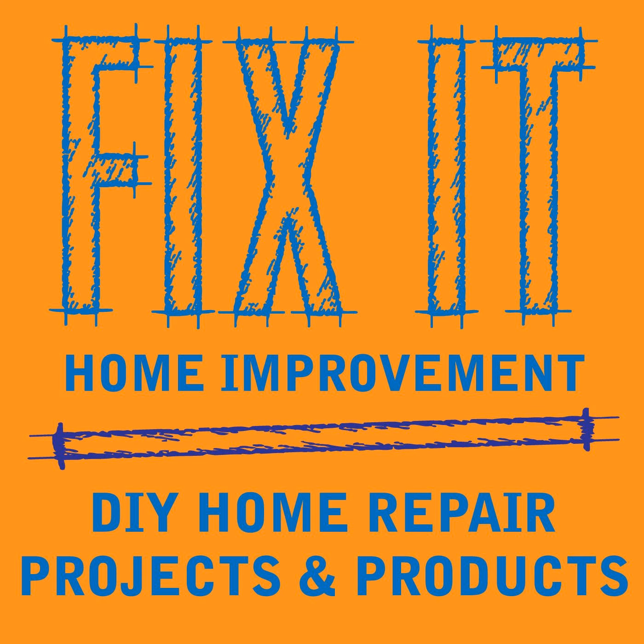The key to finding out what wires go where, let's say you removed your old outlet and you didn't mark which wires were on the line or the load side, or let's say you had a traditional outlet and now you're changing it to a GFCI, you have to know what side is line and what side is load. So you turn off the breaker to this circuit and you're going to separate all of these wires. You take off the old outlet, you separate all your wires, and now you're going to turn the power back on, so you want to make sure that those wires are not touching anything. And this is where you need an electrical tester. You're going to test the two hot wires and see which one has electricity going to it. This is your line side. You're going to mark it with a little piece of masking tape. You're going to turn your circuit breaker back off or remove the fuse, and then you're going to wire up the cable with the hot to the line side. The other cable is going to go to the load side. And now when you're connecting it like this, any of the outlets connected to that load side is actually going to be protected by this GFCI.